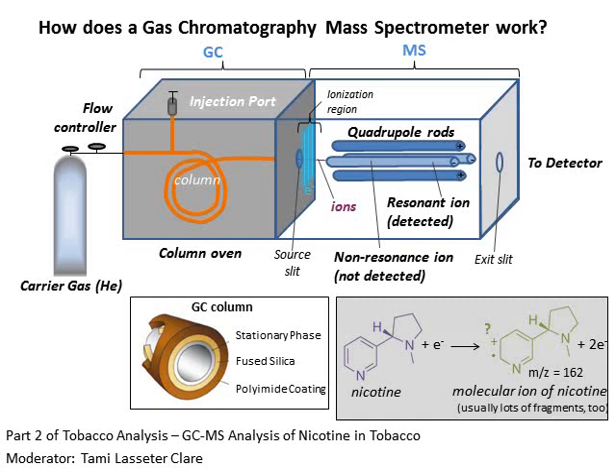The column is a glass capillary tube that is very narrow, in the range of tenths of a millimeter, and very long in the range of about 10 meters. That is to allow sufficient separation of the mixture of molecules of interest. The inside of the column is coated with a waxy mixture that provides a nonpolar surface for molecules to differentially interact with. Another key part to separating these molecules is the temperature of the oven, which gets ramped.